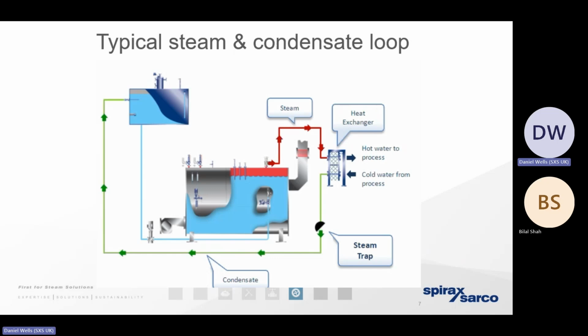Now, in the vast majority of building service and industrial applications, we're going to be using the steam for its thermal energy attributes. We're using it to heat something up. So at the opposite end of the pipework, 1,000 meters away, I'm showing a very simple, basic plate heat exchanger. So the steam as a gas is brought onto the top of the heat exchanger. The steam will pass down one side of the heat exchanger, and the water, or whatever it is that we're heating up on the secondary side, is going to run counterflow to take on all of the energy that the steam is carrying.